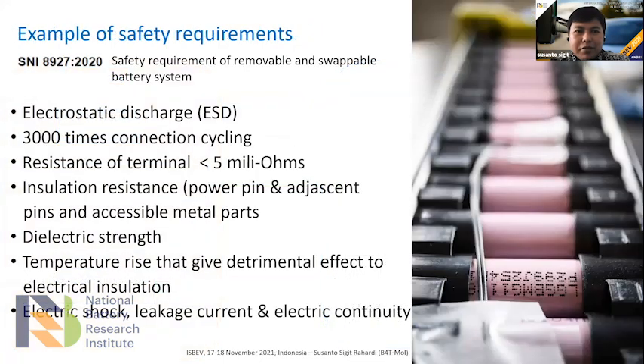For example, the safety requirement of a removable and swappable battery system includes many tests, such as electrostatic discharge, 3000 times connection cycling, resistance of terminal, insulation resistance, electric strength, temperature rise, and electric shock.